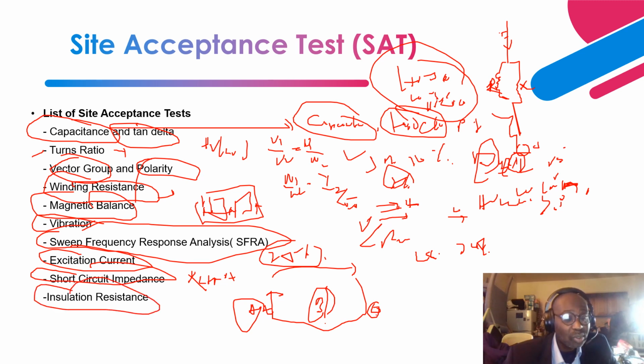Next is insulation resistance. Okay, so you do the insulation resistance to determine the contamination level, right? And also perform the polarization index, where you divide the insulation resistance at 10 minutes over the insulation resistance at 1 minute, right? To determine the contamination level on both the paper, the solid insulation, and the oil insulation. The criteria for a new transformer is to get a polarization index of greater than 2.0, right? For an in-service transformer, all you need is something greater than 1.5 and above. Anything at 1.5 and below for the polarization index requires further investigation.